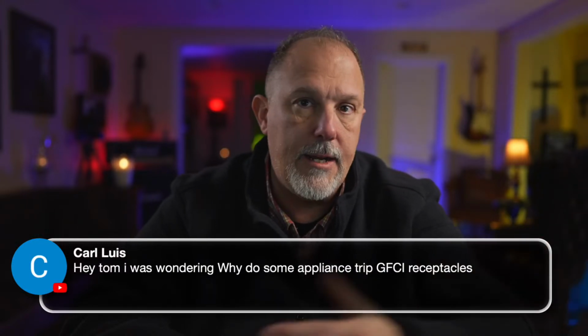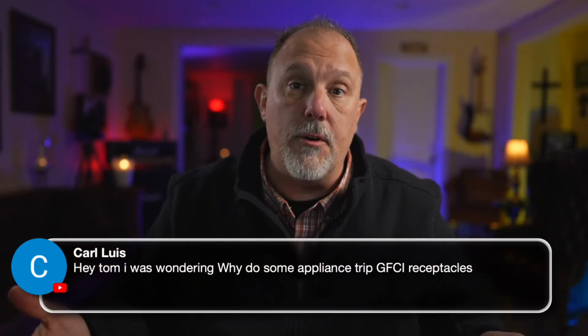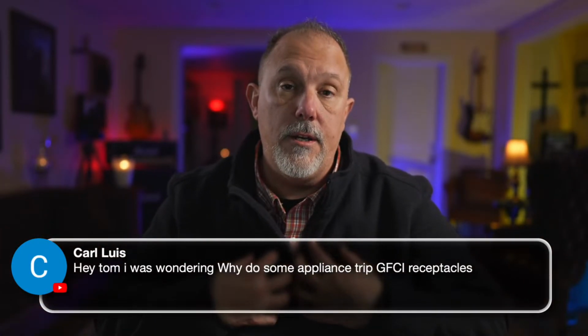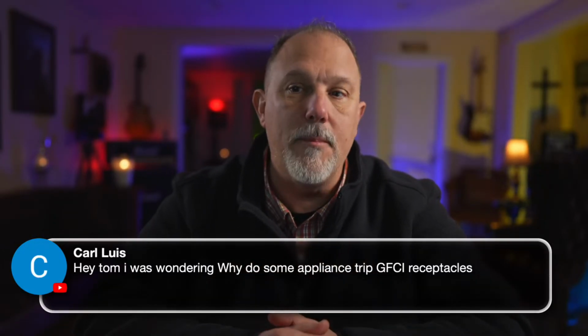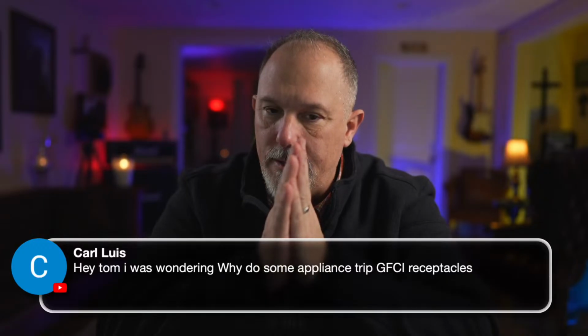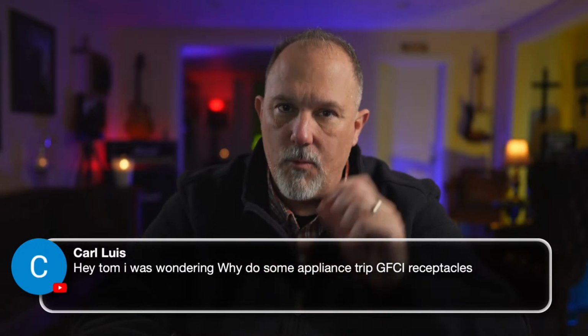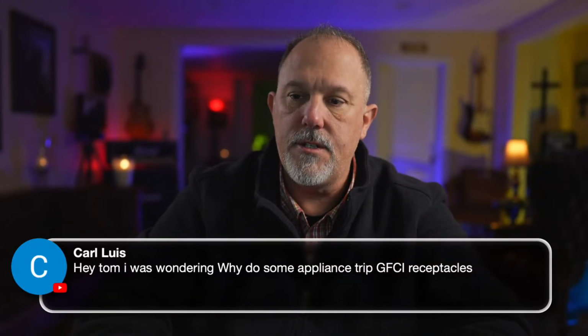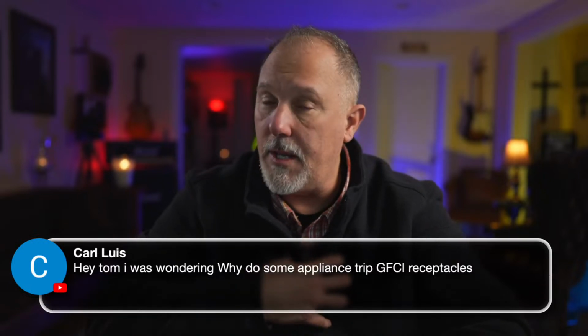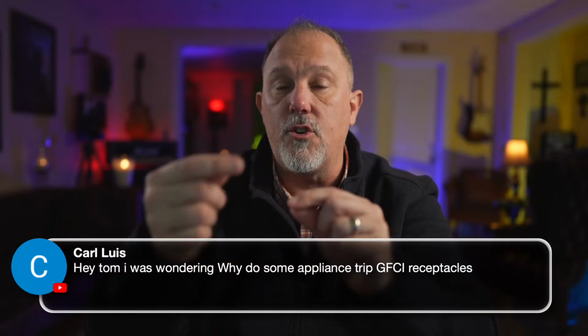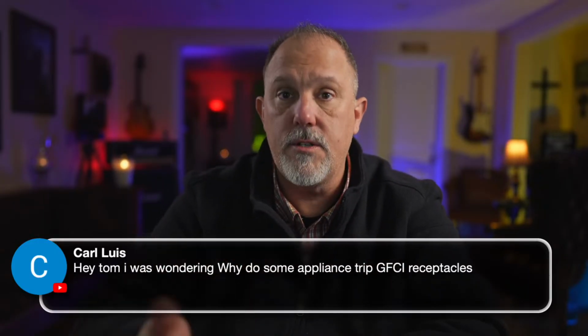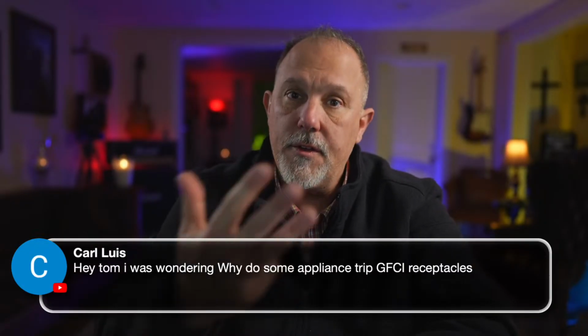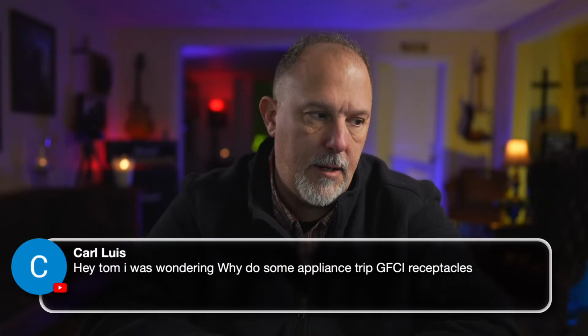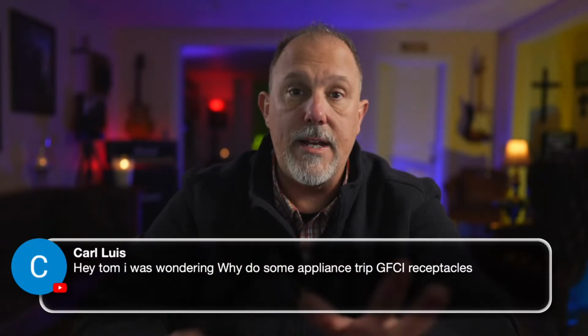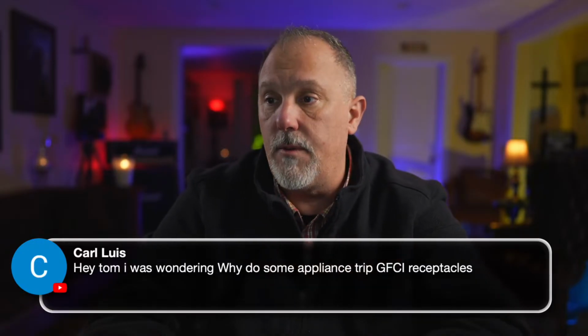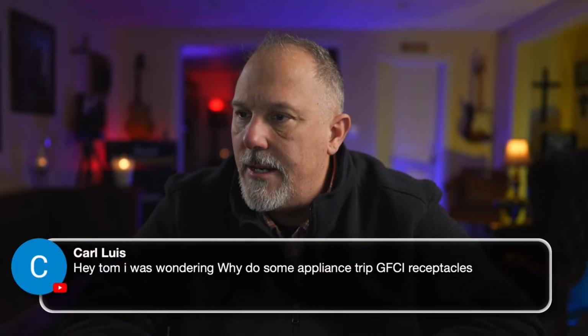Whether it be a receptacle GFCI or a breaker GFCI, GFCIs are GFCIs. They respond to current going outside the path, and they're there to protect the human body based upon the human body's damage curve. So those are the three things that I'm aware of. One is a true ground fault. The other is high frequency, and in my opinion, it's that leakage current that's going to the equipment grounding conductor and not the neutral. It should be going to the neutral, because there is no neutral. And the third reason is this burn-in that I'm telling you about, a process for specific manufacturers for whatever reason. That's sort of the background that I know about. I'm not familiar with anything else. Oh my gosh, I have to turn my volume on.